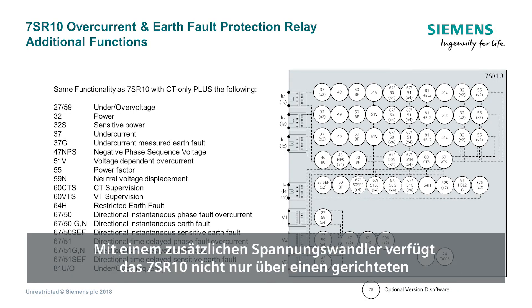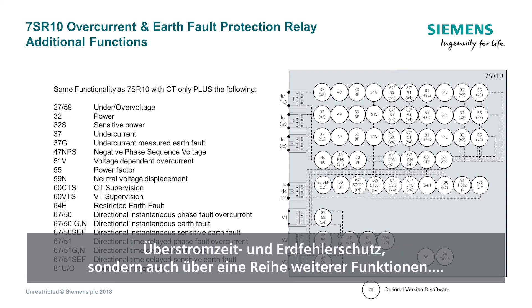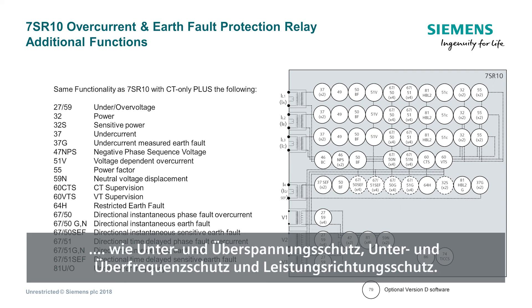With the addition of voltage transformers, the 7SR10 not only provides directional overcurrent and earth fault, but a number of additional functions. These include under and over voltage, under and over frequency and directional power protection.